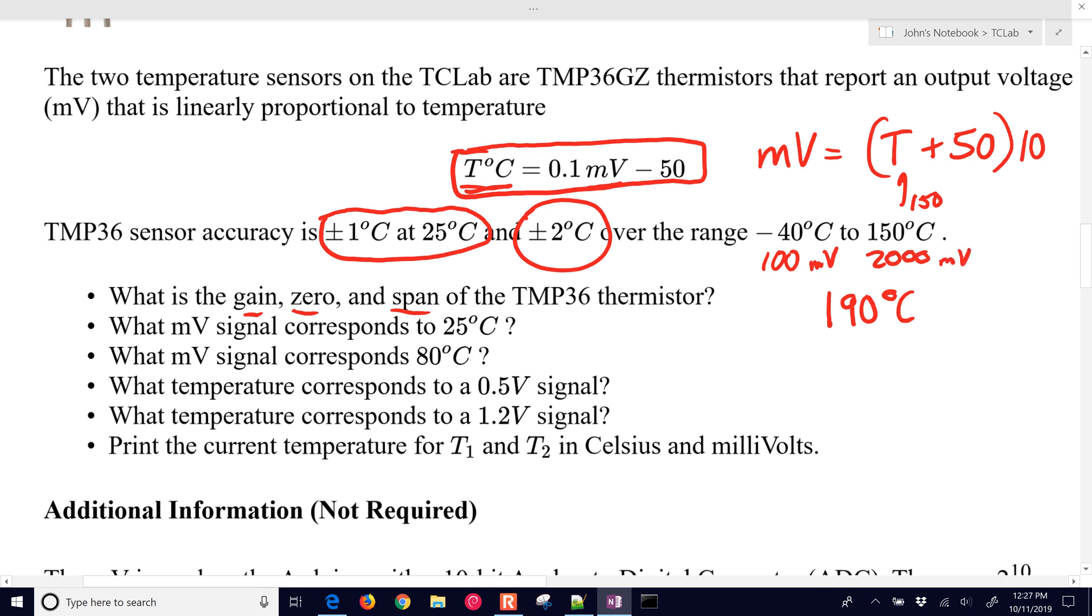To come up with our gain, I'll do Km, and that is going to be the 2,000 millivolts minus 100 millivolts divided by 150 degrees C minus negative 40 degrees C. And so, that is going to be 10, and don't forget the units on here, millivolts per degree C. There is our gain.